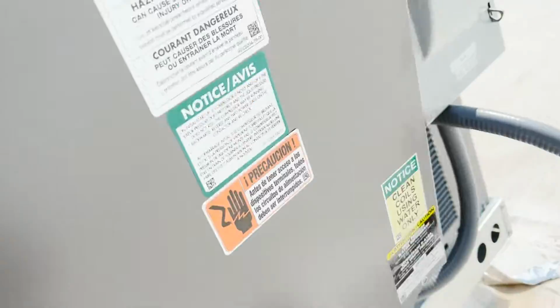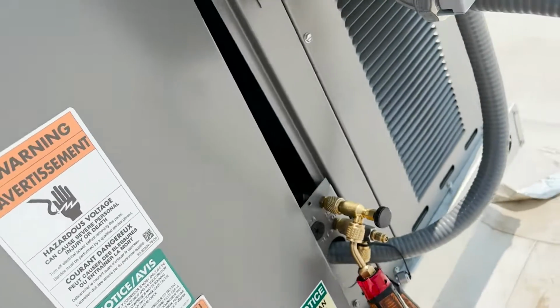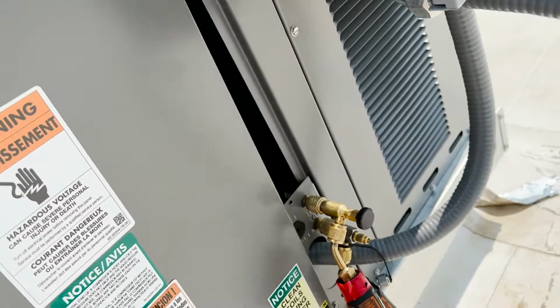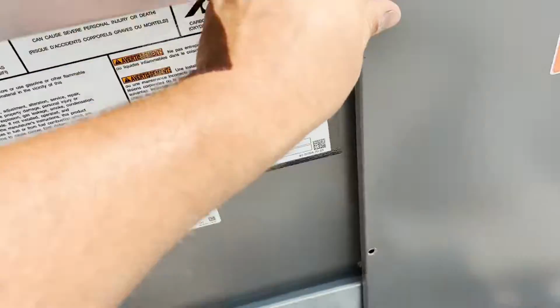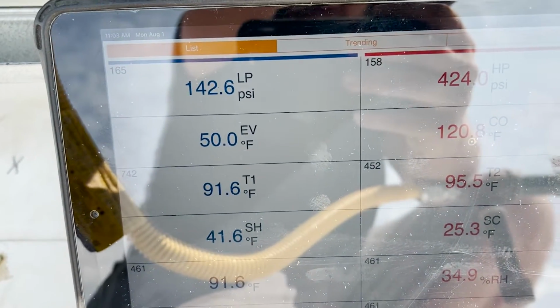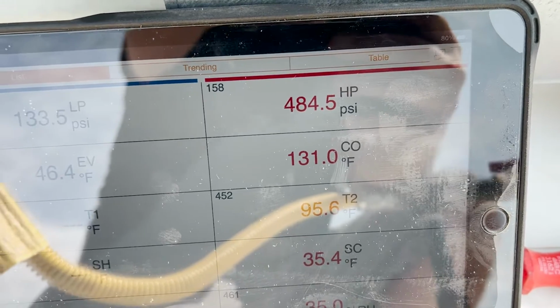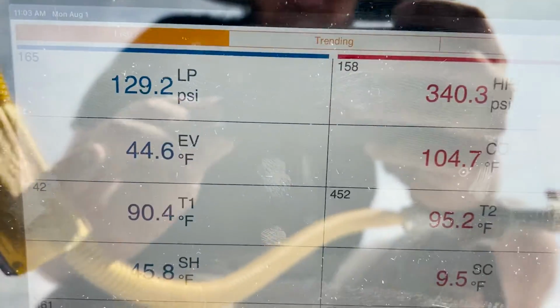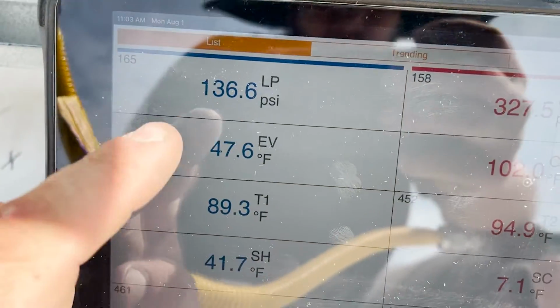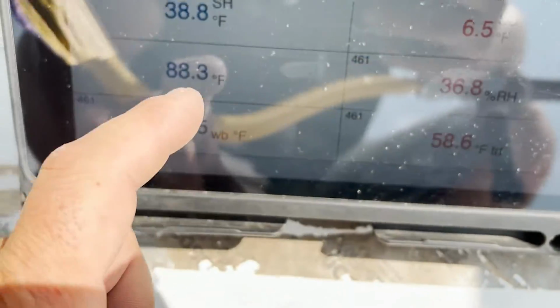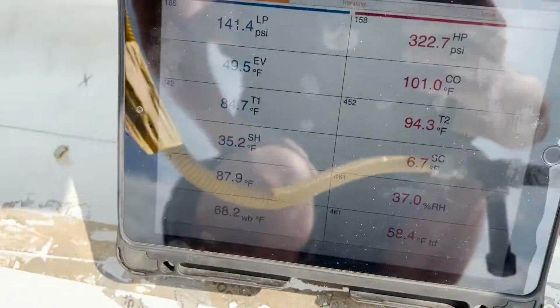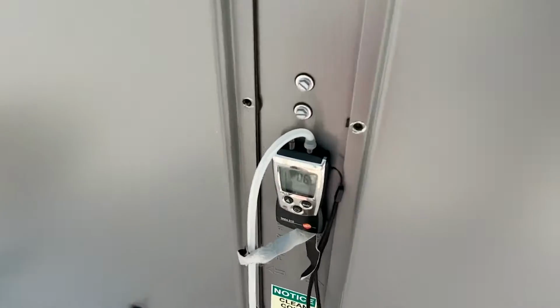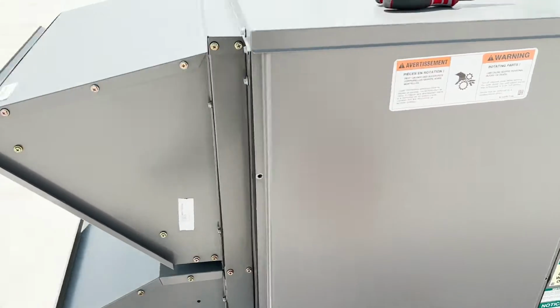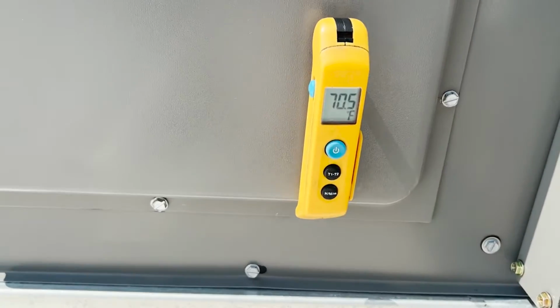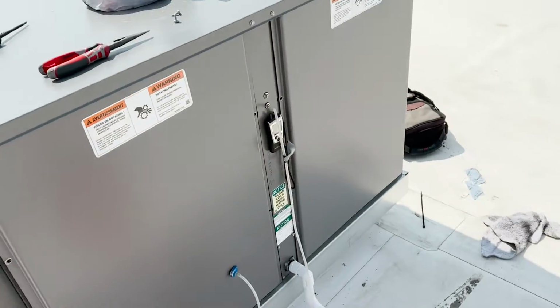Let's get our door panel in place enough to cover the air. See how our low pressure is coming low and our high pressure is going way up? Okay, my blower came on and took care of that. You stay there, man. Now we're gonna let this run for a minute. We have our superheat and our subcool is coming around, and then this bad boy is in our return air, just to get a more accurate return temperature. At the same time, we're gonna go ahead and do our static pressure readings. And then I also have my temperature probe in the supply so that I can get my delta T. So try to do as many things at a time as possible.